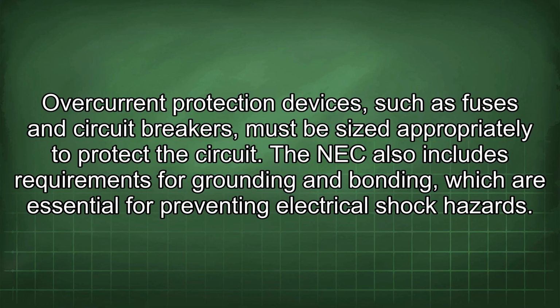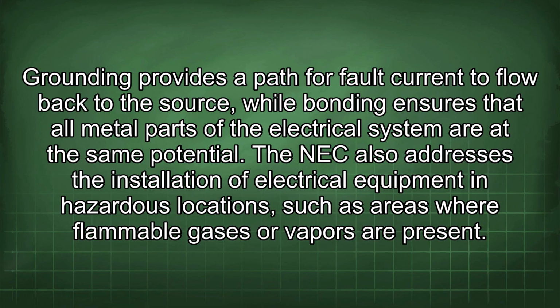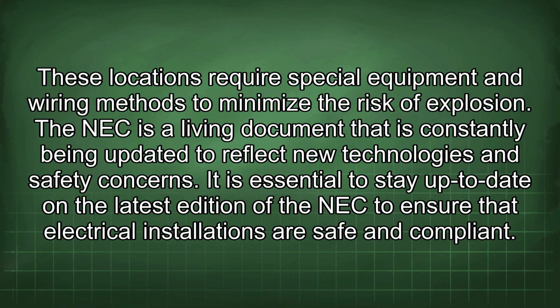The NEC also includes requirements for grounding and bonding, which are essential for preventing electrical shock hazards. Grounding provides a path for fault current to flow back to the source, while bonding ensures that all metal parts of the electrical system are at the same potential. The NEC also addresses the installation of electrical equipment in hazardous locations, such as areas where flammable gases or vapors are present. These locations require special equipment and wiring methods to minimize the risk of explosion.